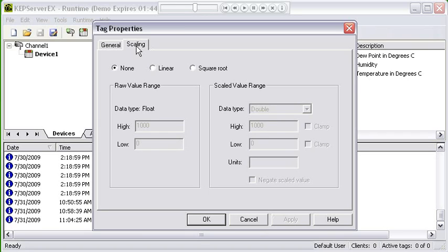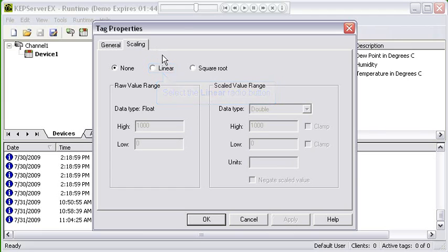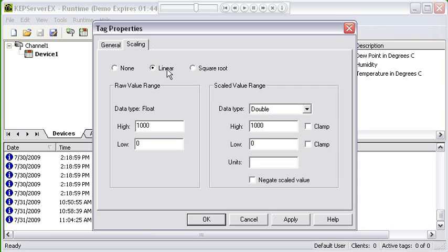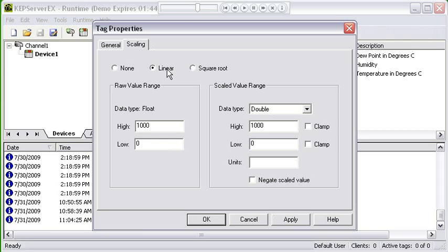Square root scaling provides high precision. Linear scaling is pretty much a linear mathematical function. For instance, if I was scaling a tag from 0 to 1000 to 0 to 100, it would literally be dividing the raw value by 10 to get the new value. The way it works is you have your raw value which is what's coming in to the server. In this case it's float, but say I had a sensor that was sending floating point data in raw format, in integer format.